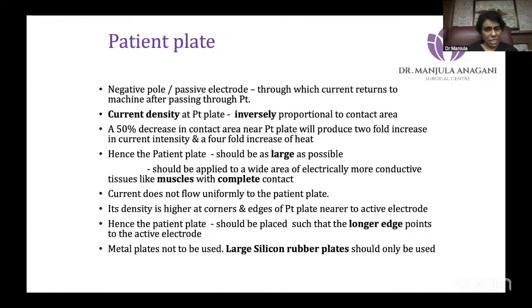And it should be on the muscle, not under the buttock where the liquid will come in between and the contact area is going to be less. So, it should be on the anterior part of the thigh, away from the liquid water or any betadine which goes inside, and complete contact, and current does not flow uniformly. At the edges and corners, it is more. So we should put it in a way that longer edges point towards the active electrode.